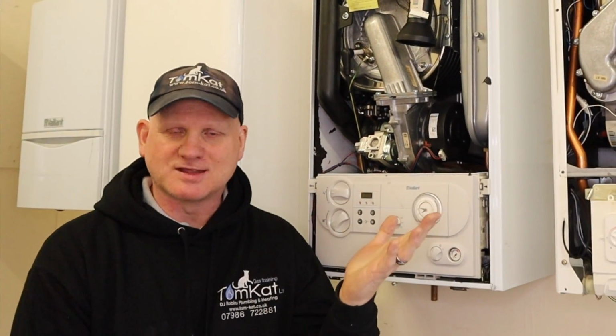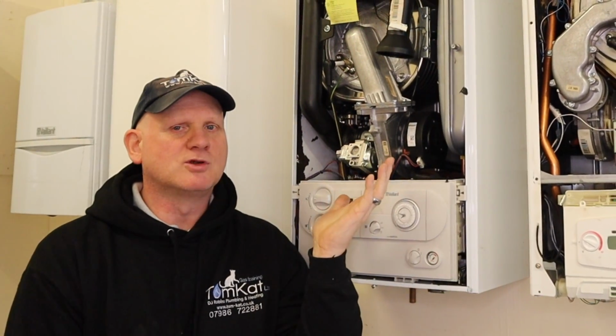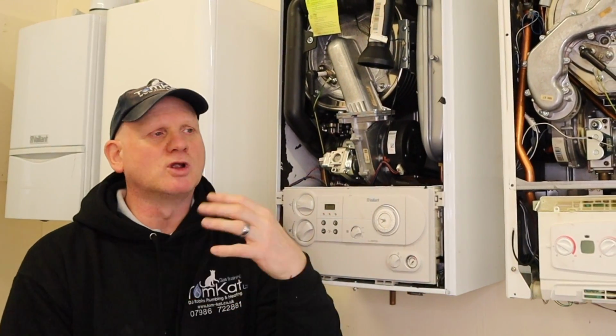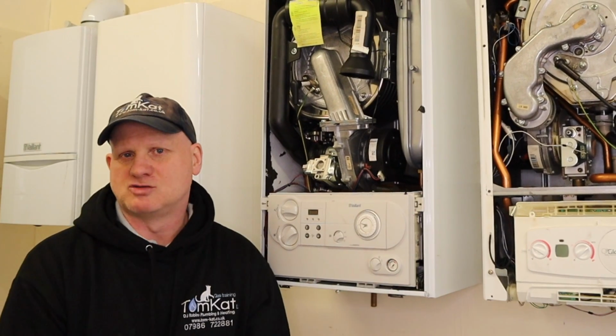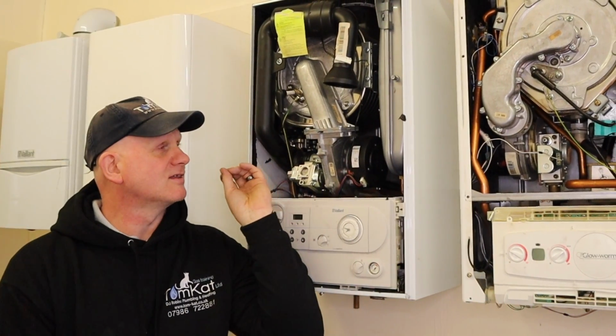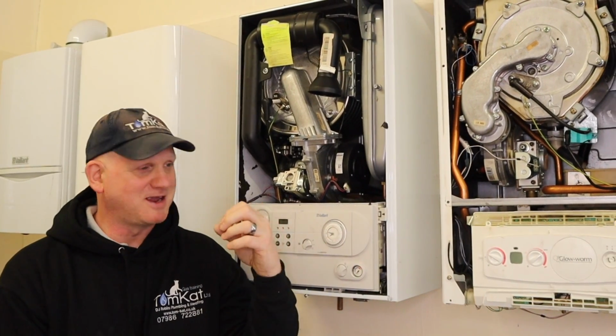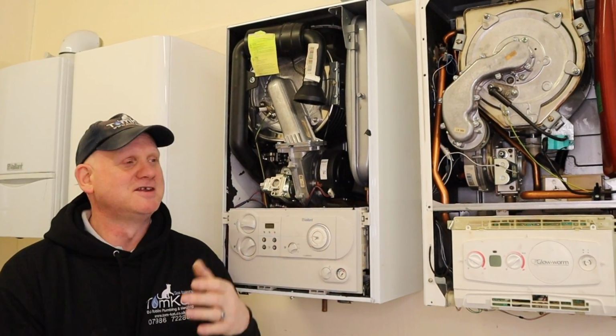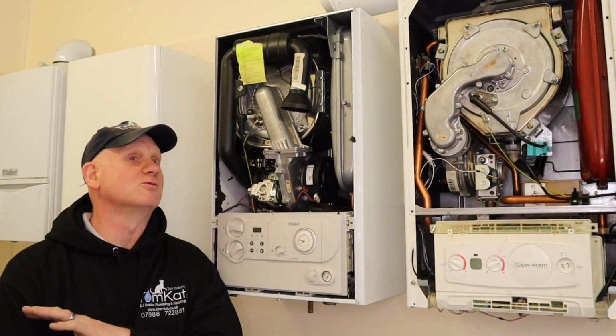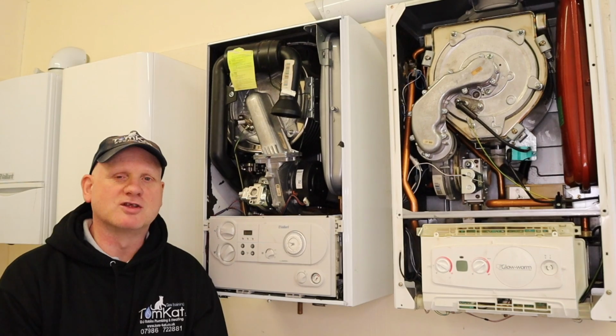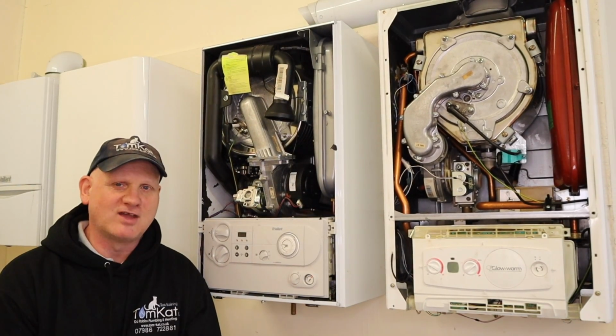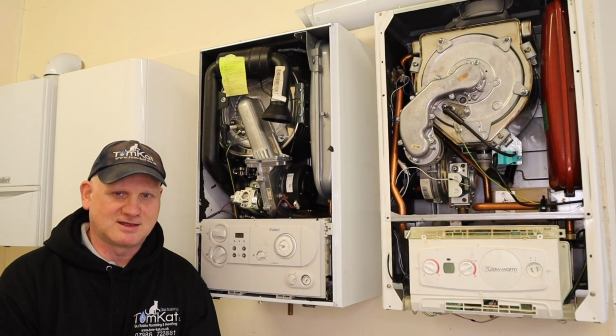Now compared to aluminium, stainless steel has a larger band for the pH level. Basically a stainless steel heat exchanger doesn't need inhibitor in it, but because we've got copper and steel in the system along with the stainless steel, we will need to put inhibitor into the system. Aluminium will always need inhibitor putting in because of the galvanic corrosion. So that's another thing: if we had stainless steel pipes, stainless steel radiators, stainless steel fittings and stainless steel heat exchangers, then we wouldn't need to put inhibitor into our system. Because we haven't got that, we need to make sure we still monitor our pH levels in the water, and we still need to fit a magnetic filter even on a stainless steel heat exchanger.